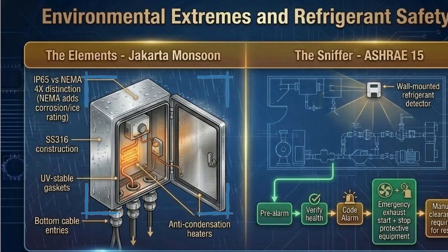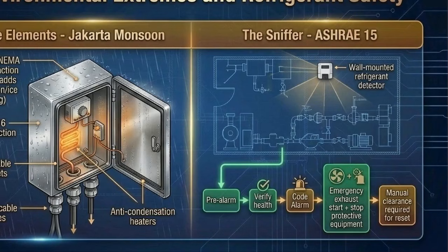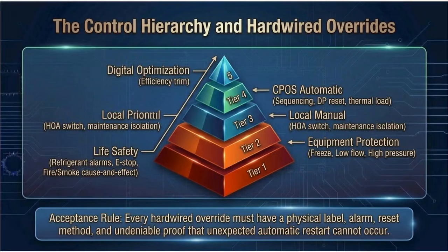Inside, ASHRAE 15 protocols dictate life safety. Wall-mounted sniffers detect toxic leaks, immediately starting emergency exhaust and stopping protective equipment. This pyramid maps the facility control hierarchy. Life safety and equipment protection always hold supremacy over Tier 5 digital optimization. The base acceptance rule dictates every hardwired override must have a physical label, an alarm, and undeniable proof an unexpected automatic restart cannot occur.